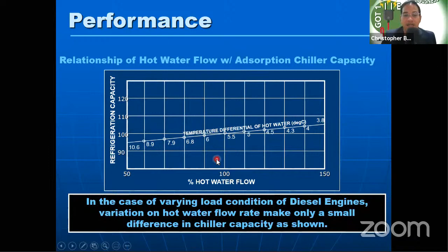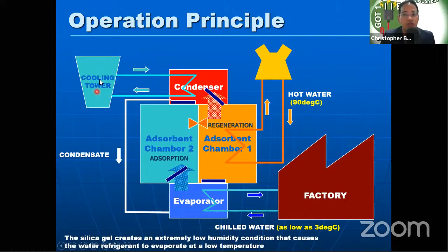So ang operation, simple lang. May dalawang chamber lang na palipat-lipat. Sa absorption chiller at adsorption or heat recovery chillers, kailangan mo may dalawang chamber palagi: isa mag-absorb o mag-adsorb, yung isa naman magre-regenerate para magamit mo uli siya next time. So using a cooling tower or a radiator, yun yung tutulong sa regeneration process. Okay?